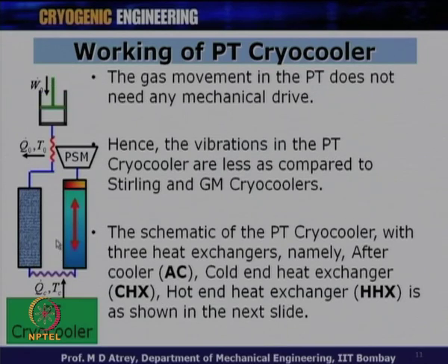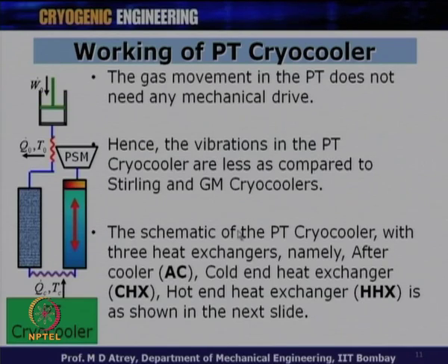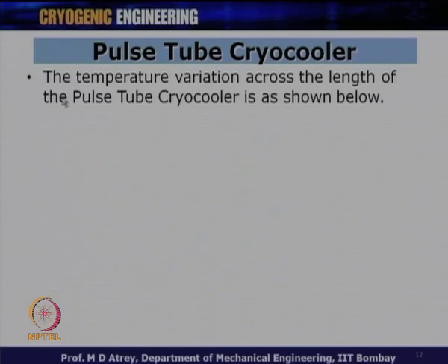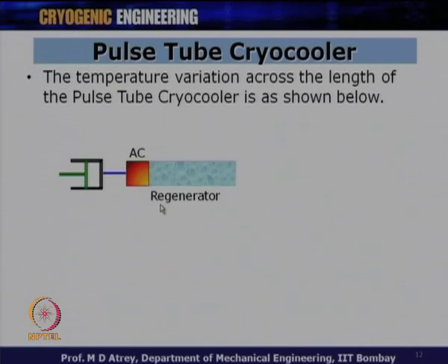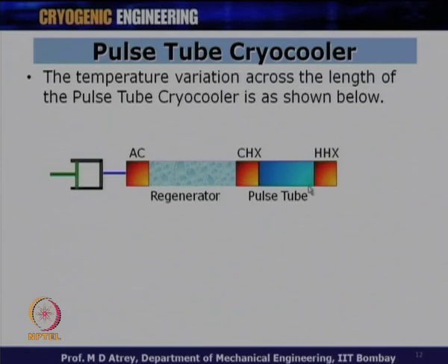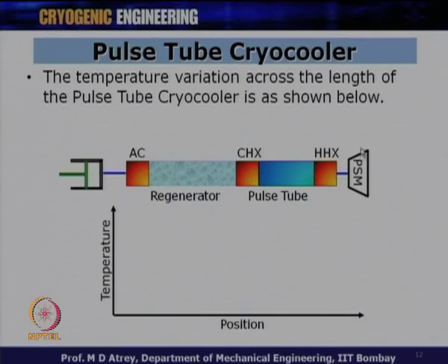The schematic of the pulse tube cryocooler with three heat exchangers — after cooler (AC), cold end heat exchanger (CHX), and hot end heat exchanger (HHX) — will be shown in the next slide. The components in line are: compressor, after cooler, regenerator, cold end heat exchanger, pulse tube, hot end heat exchanger, and PSM. This is called the inline configuration of the pulse tube, where gas travels in a straight line and returns in a straight line.